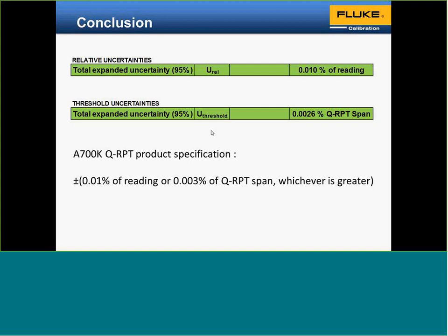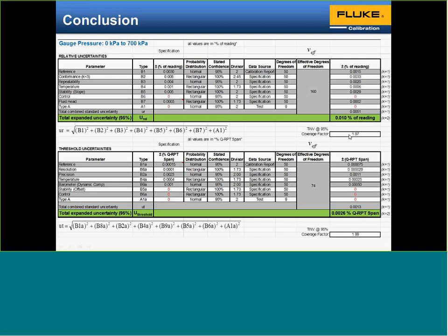So the value for my 95%, I'll show you the spreadsheet. For the degrees of freedom for each contributor, we use the Satterthwaite formula to come up with effective degrees of freedom and the total uncertainties. With the effective degrees of freedom, the weight of each contributor and its uncertainty, for K I might have 9, but that's 0 here, so it really doesn't influence me. But if a contributor impacts your overall uncertainty where your K factor might be larger than 2.